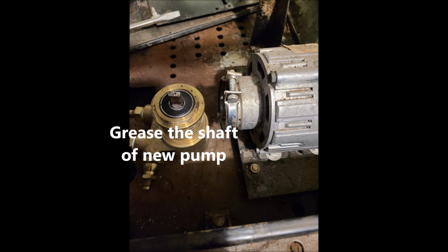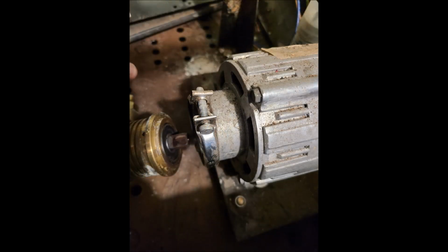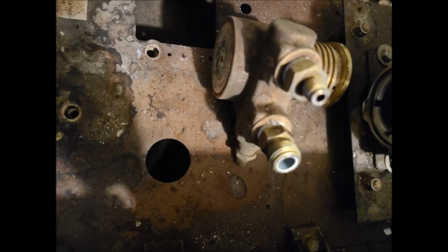Add a small amount of grease on the shaft of the pump, then slide it onto the motor. Quick tip: I like opening the clasp until the screw barely holds it on. That makes it a lot easier to clasp it around the motor and pump. Tighten the clasp until you can still turn the pump head. Notice the fan and the rod of the motor will turn with you.